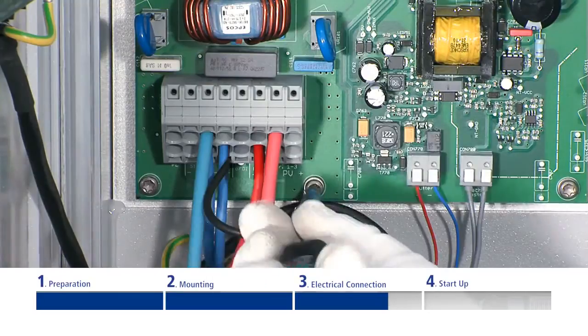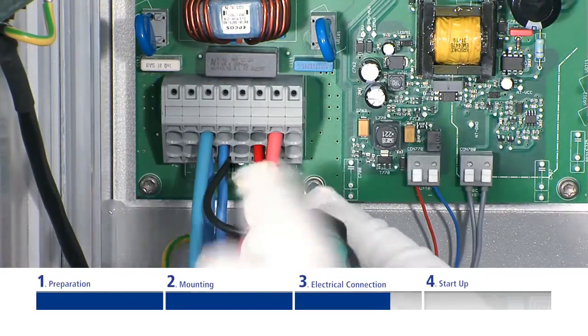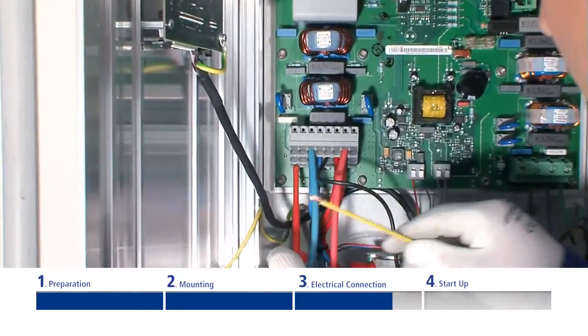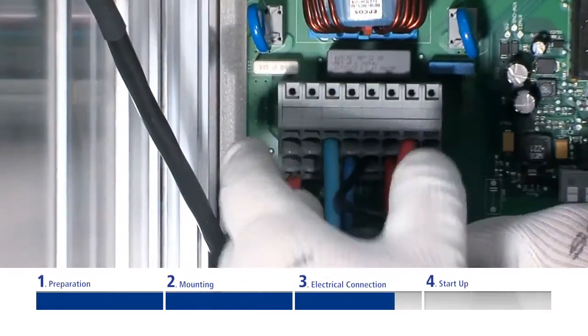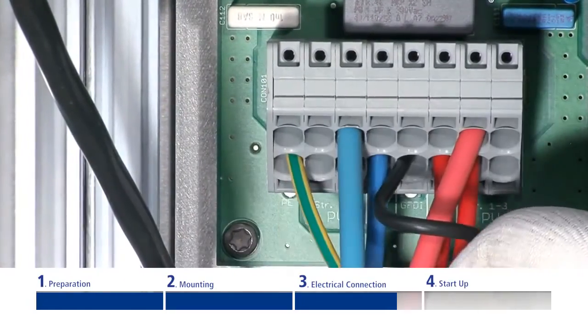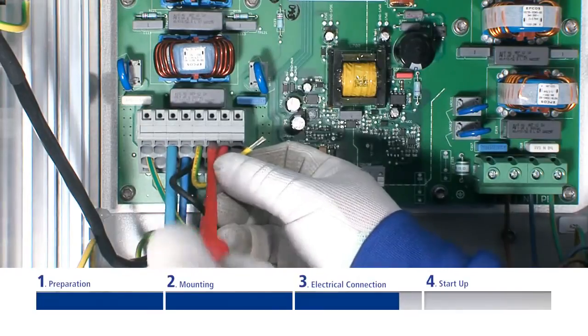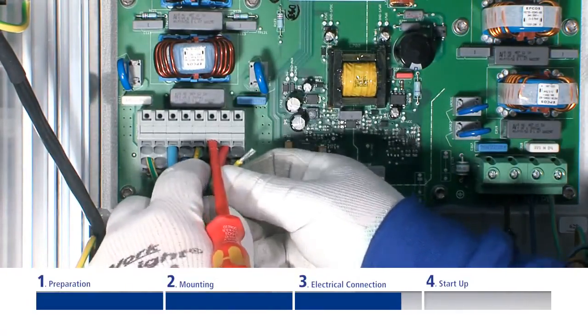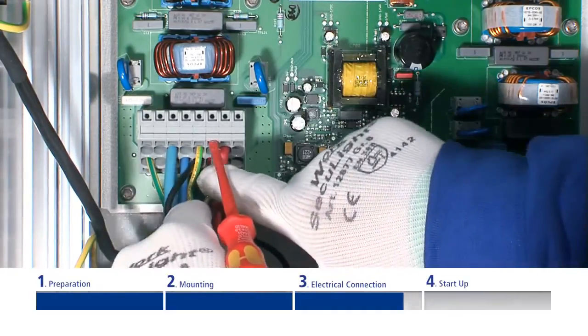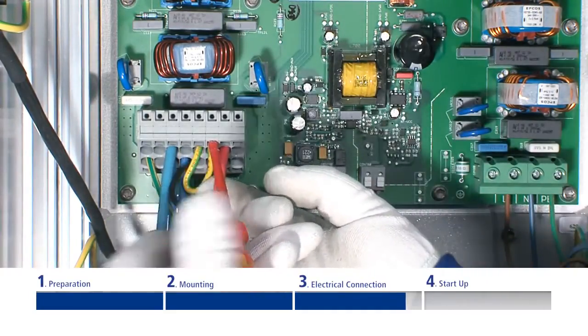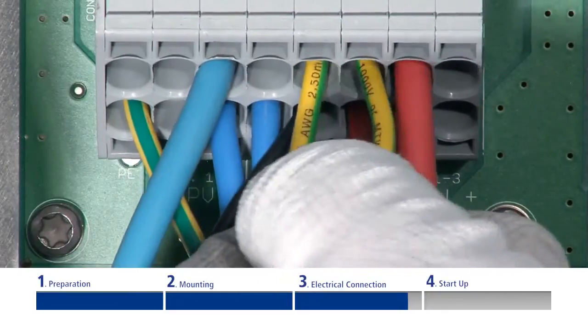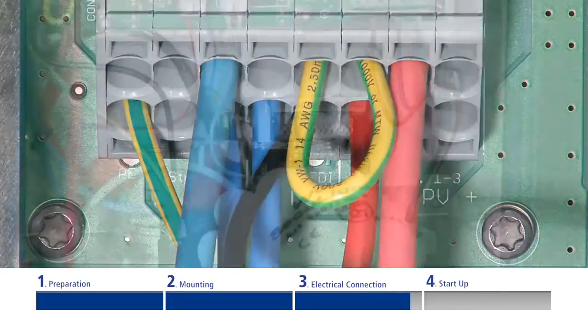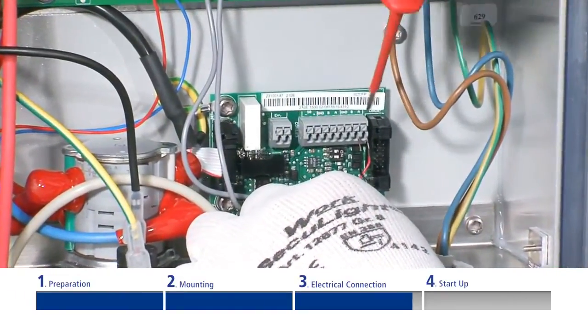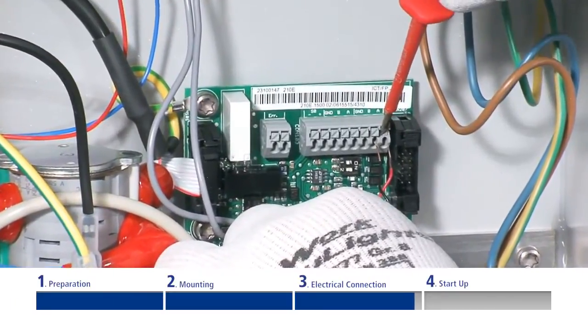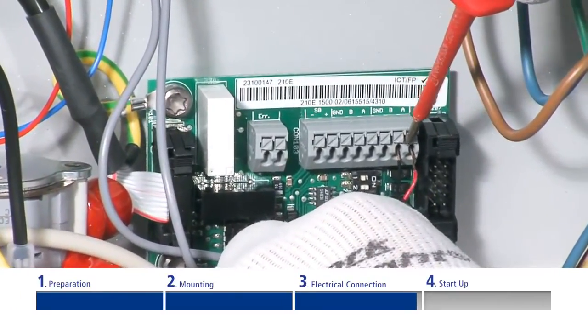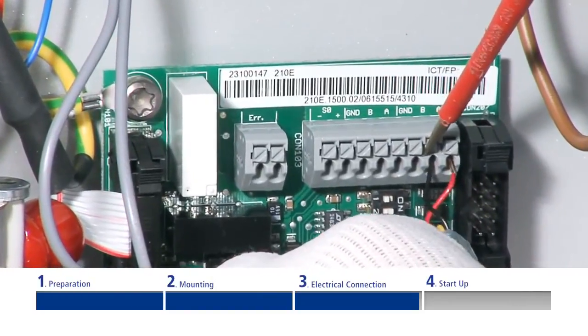Attach the PE cable, green-yellow, to the corresponding PCB fitting using the cable shoe, or depending on the model, directly into the PE terminal on the PCB board. Clamp the enclosed cable bridge in the upper GFDI terminal and the DC plus or DC minus terminals, depending on whether positive or negative earthing is required. Earthing monitoring is to be activated after startup via the display. In order to facilitate communication between the inverter and the accessories, connect a 2-core cable to the RS485 interface terminal on the control card.